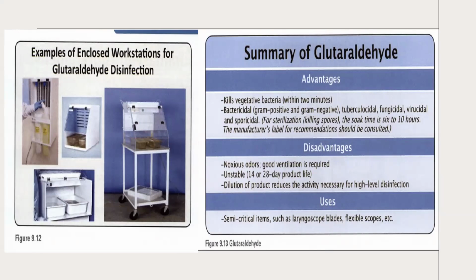14 to 28 day product life. That is when you begin to use it. Of course, dilution of the product reduces the activity necessary. Because of the dilution, that is why you do the test strip, which is the MEC, minimum effective concentration. You check it to see if the concentration is still at the level where it can do its job. That's about that. Uses, of course, are semi-critical items such as laryngoscope blades and also flexible scopes, etc.